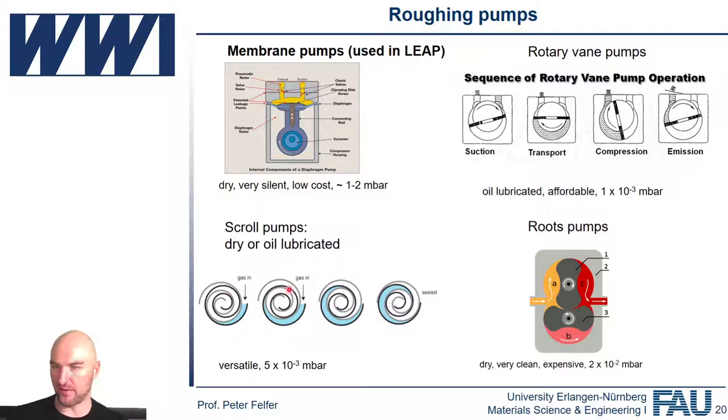They are very versatile pumps, and they get you to about 5 × 10⁻³ millibar, 10⁻², 10⁻³ millibar, so also very good vacuum. The downside is that they are significantly more expensive, 4,000-5,000 euros. So here we're talking maybe 1,000 euros, 1,500 euros, same about here. Here we're talking 4,000-5,000 euros, 3,000 at least.